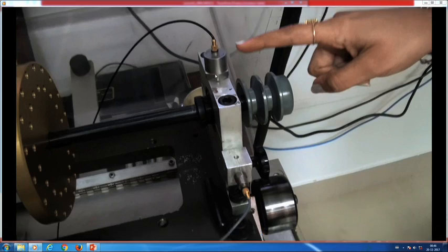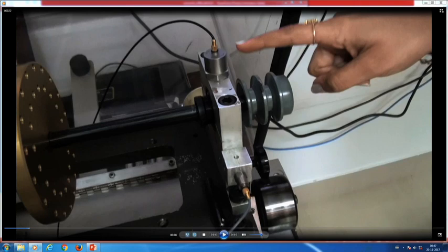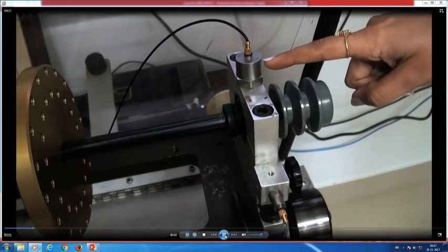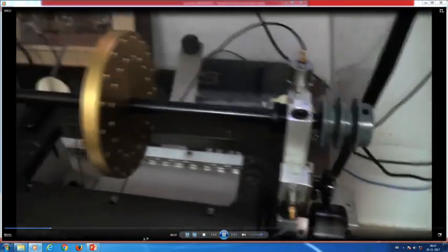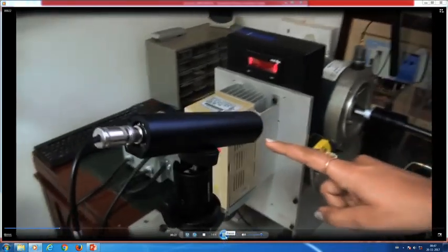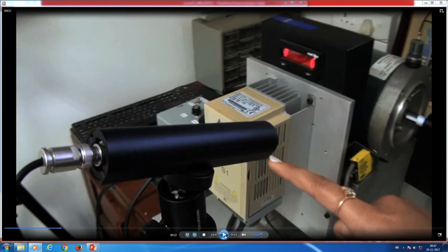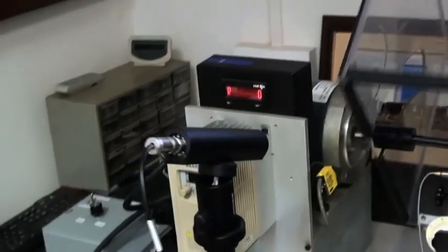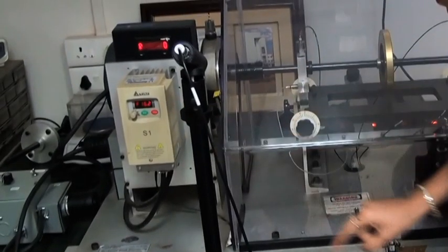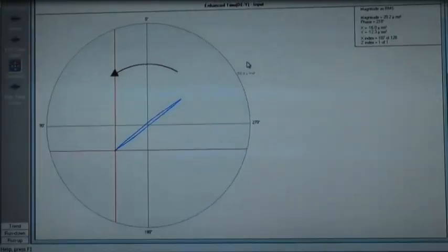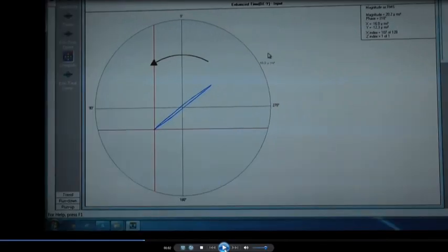These are actually accelerometers, but once we have the acceleration, we can integrate it to get the velocity, and then another integration, we can get the displacement. So, this is going to rotate. And this is a photo tach which is used to measure the rotational speed. And now this is going to run. If you see here, this is the orbit between the x and y transducers, and you can see a value here.